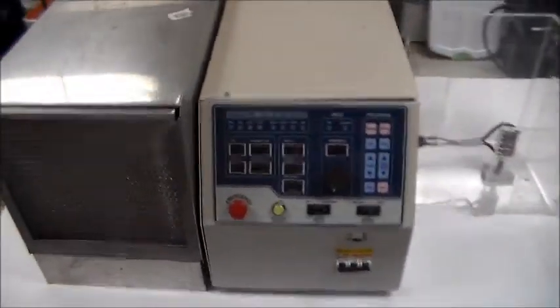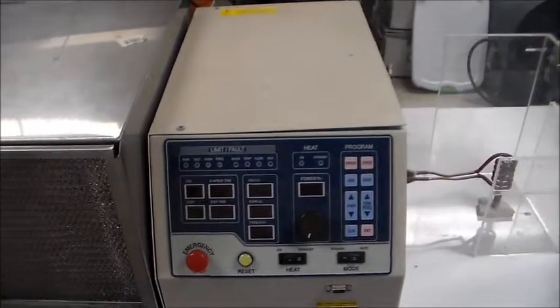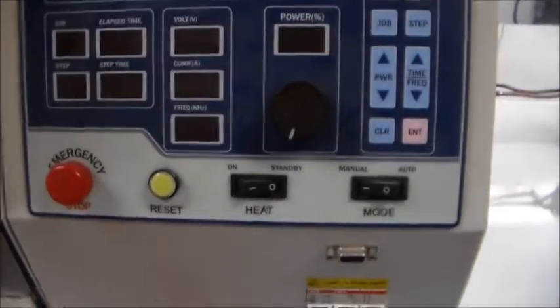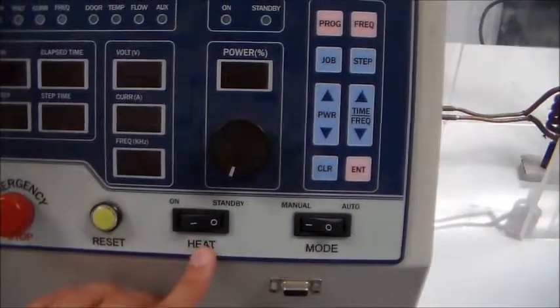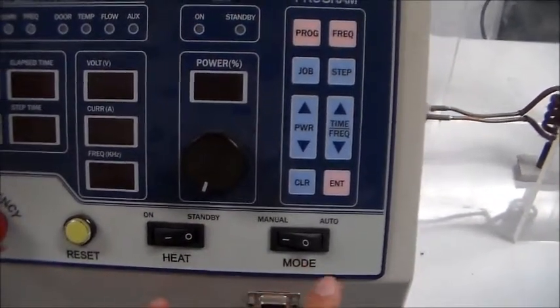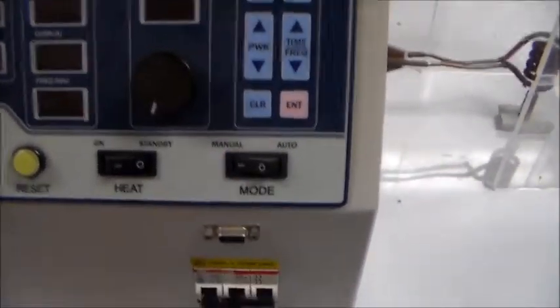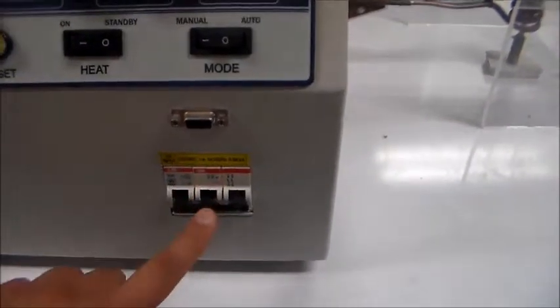Second, make sure that the switches in the control panel are in the following positions. The heat switch should be on the standby position, the mode switch should be in the manual position, and the main power breaker should be downwards.